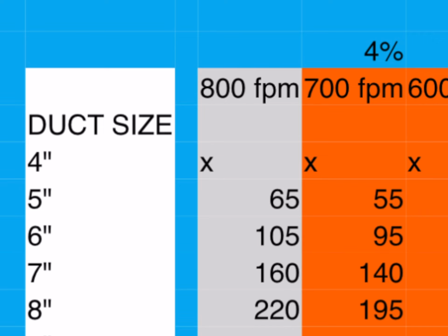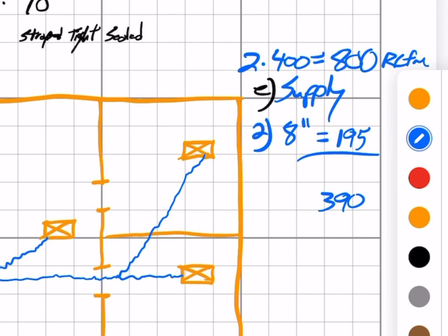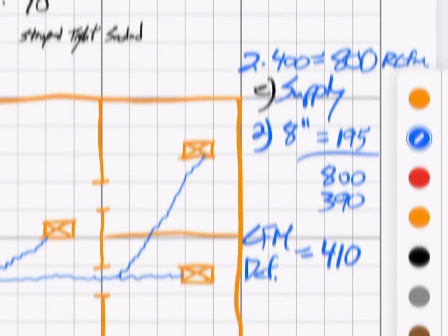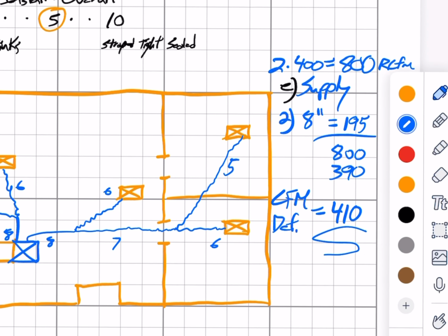Now we need to calculate the CFM deficit on the supply side. So we had 2 8-inch ducts. We're going to use 700 feet per minute on the supply side. 8 inches, 700 feet equals 195 CFM per duct. Let's multiply that times 2, which equals 390. Then we're going to take our 800 CFM minus 390, giving us the deficit of 410 CFM.